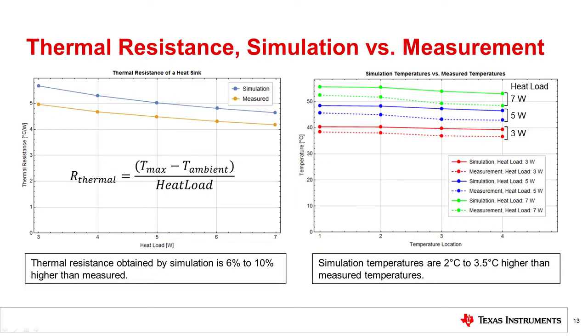Thermal resistance is calculated as maximum temperature difference divided by the heat load. Results obtained by the simulation are 6 to 10 percent higher than the measured values, which we consider to be a good match. Simulation shows 2 to 3.5 degrees Celsius higher temperatures when compared to measurement. Simulation error is in conservative direction, which is a good thing and makes our margin that much larger.